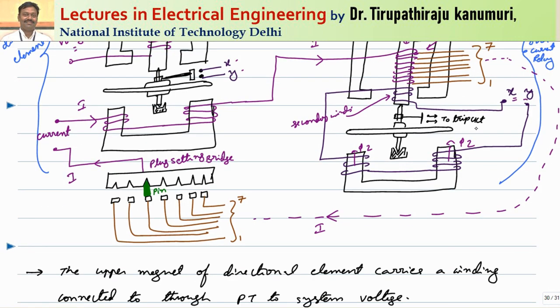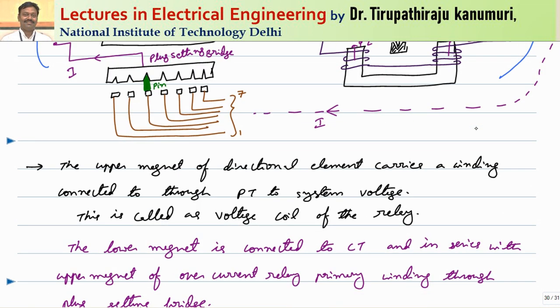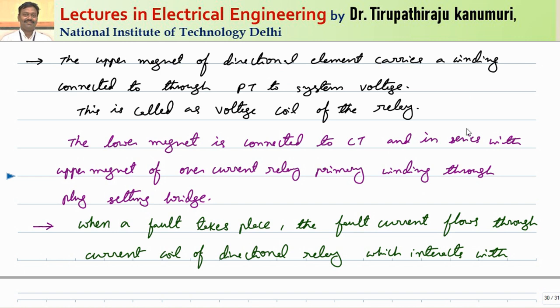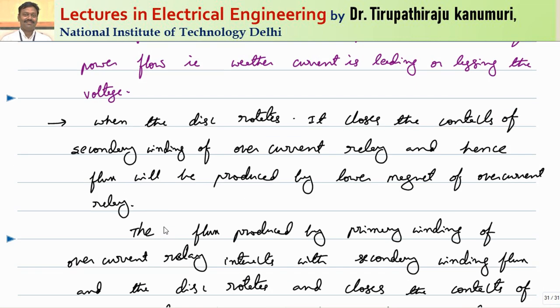The overcurrent relay operation has already been discussed. In this class we are only discussing the properties of the directional relay — its characteristics and how to adjust the angle. To summarize: the upper magnet of the directional element carries a winding connected through a potential transformer to the system voltage — this is the voltage coil. The lower magnet is connected to the CT and in series with the upper magnet of the overcurrent relay primary winding through the plug setting bridge. The disk rotates only if torque is produced in a particular direction, which depends on whether the current is leading or lagging the voltage.